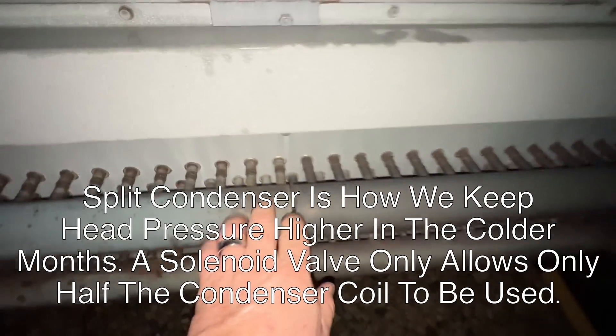Okay, we got one fan running. It's not a lot. So we're coming up cold on this one and that one. This one here is pretty warm and that's going back mediocre. I don't think they even got a split on this thing at all. Those are colder — unless they're splitting them down there. Yeah, they're split. Alright, good. So for all we know it could be that one there is trapped. Let's turn those fans off until this starts getting warm coming back, and then we should go back down there and check it.